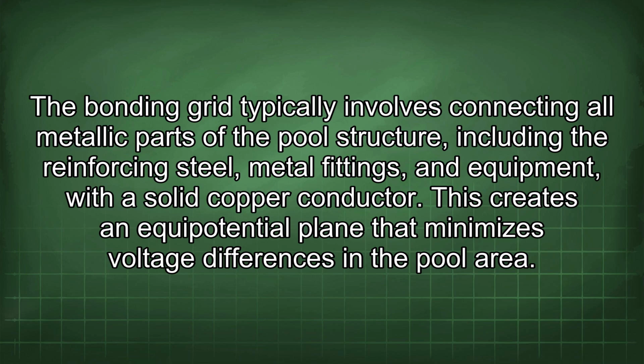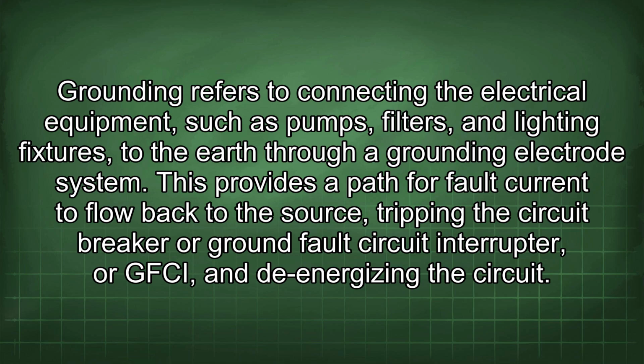The bonding grid typically involves connecting all metallic parts of the pool structure, including the reinforcing steel, metal fittings, and equipment, with a solid copper conductor. This creates an equipotential plane that minimizes voltage differences in the pool area. Grounding refers to connecting the electrical equipment, such as pumps, filters, and lighting fixtures, to the earth through a grounding electrode system. This provides a path for fault current to flow back to the source, tripping the circuit breaker or ground fault circuit interrupter, or GFCI, and de-energizing the circuit.